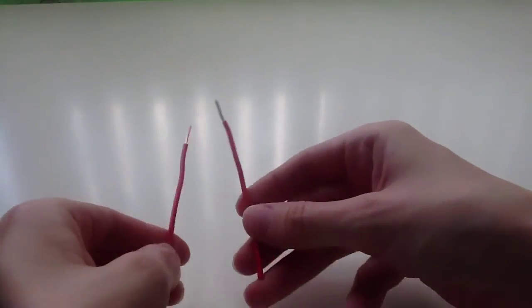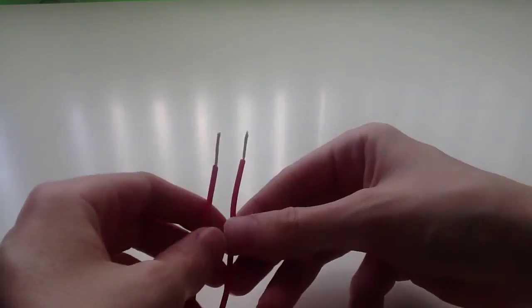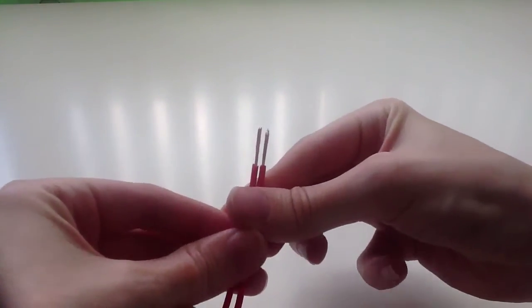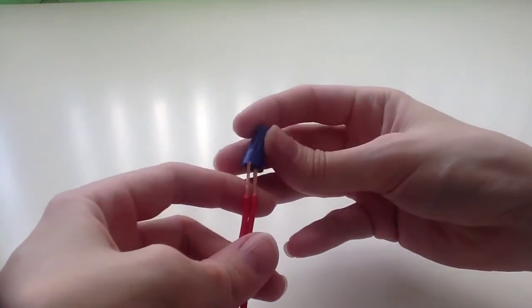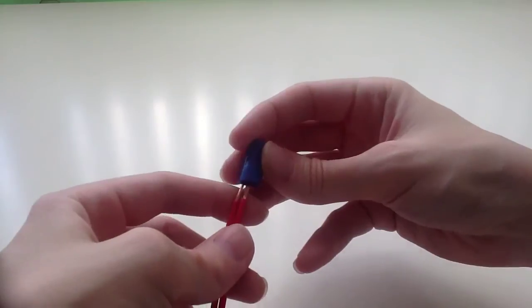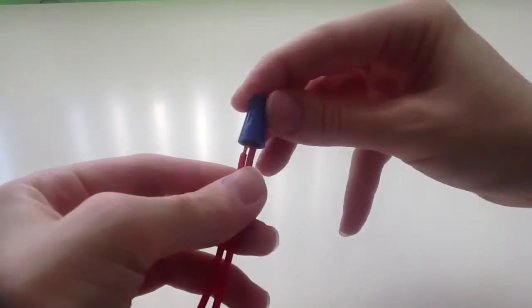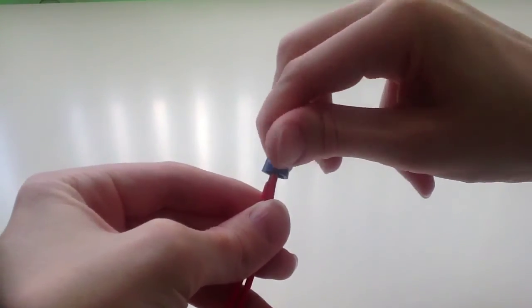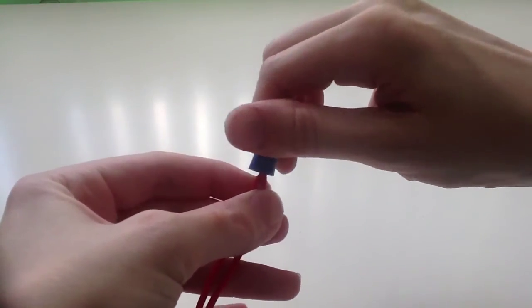For the next part of this activity, we're going to install a wire nut. It's a connector for two wires. I've stripped 3 fourths an inch to an inch off of both of these wires. You assemble them together like so. Take the wire nut. Make sure they're tightly in there. Turn and turn. Continue to turn until you see the wire twists two times.